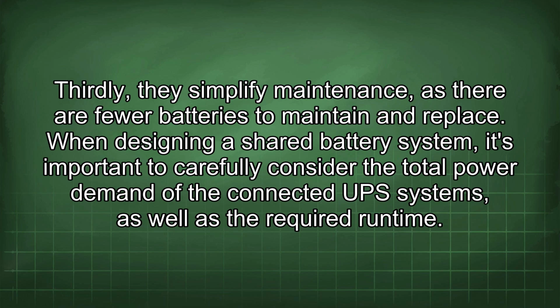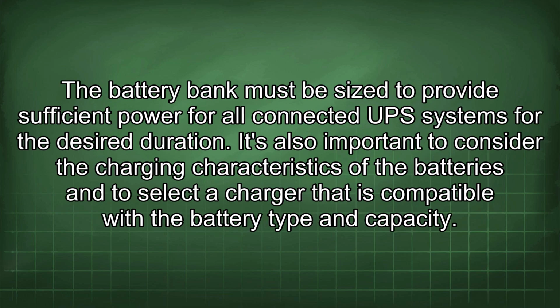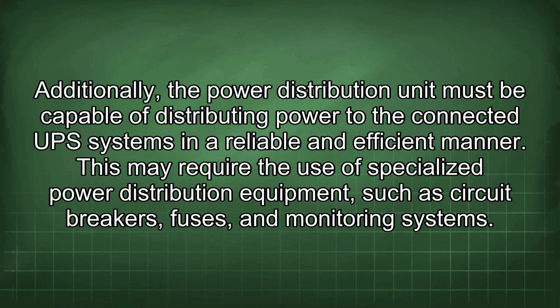When designing a shared battery system, it's important to carefully consider the total power demand of the connected UPS systems, as well as the required runtime. The battery bank must be sized to provide sufficient power for all connected UPS systems for the desired duration. It's also important to consider the charging characteristics of the batteries and to select a charger that is compatible with the battery type and capacity. Additionally, the power distribution unit must be capable of distributing power to the connected UPS systems in a reliable and efficient manner. This may require the use of specialized power distribution equipment, such as circuit breakers, fuses, and monitoring systems.